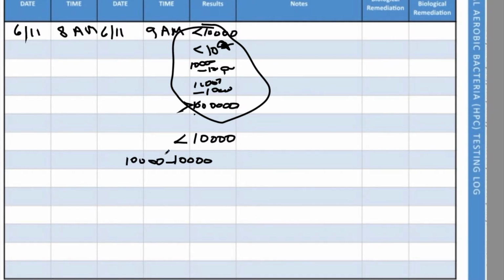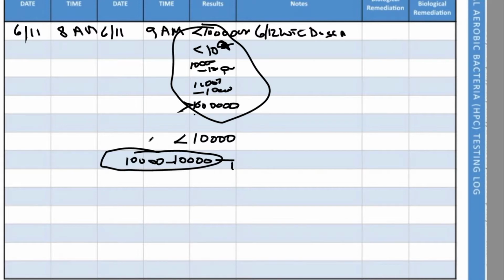...it's a pretty simple remediation. You call your water treatment company, let them know, and they arrange for you to either adjust the biocide feed or add an additional dose of biocide. That's enough to satisfy the Department of Health. You should record in here that on 6/12 your water treatment company came in and dosed the system in response to that high bacteria count if it's greater than 10,000. Similarly, 100,000 is a little bit more that you have to do.